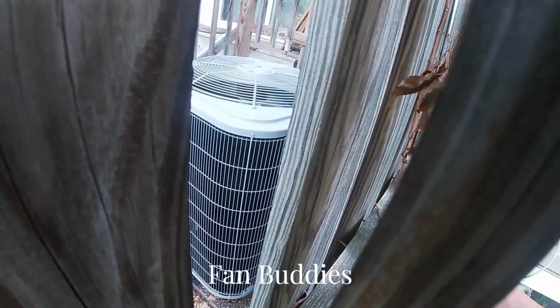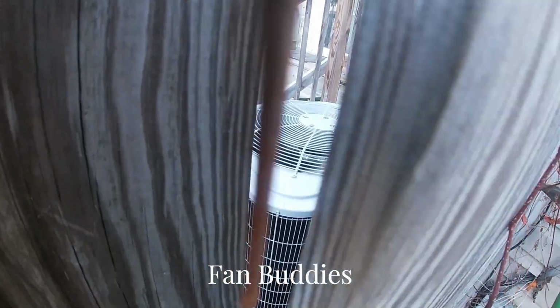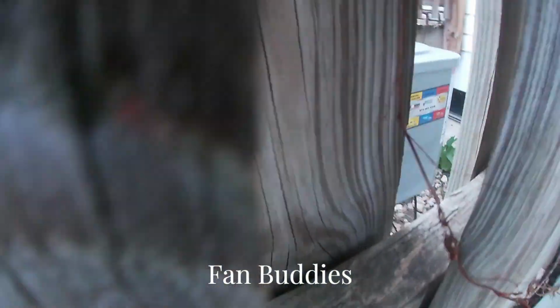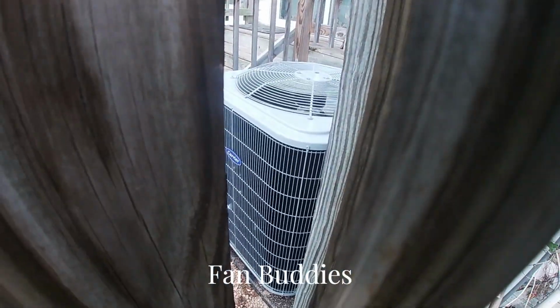It's a brand new Carrier Comfort Series air conditioner. I'm pretty sure that's a Copeland scroll. And this thing is from, yep, 2024. My first 2024 unit. If I zoom in here, you may not be able to see it that well, but it says 20224, so the 20th week of 2024. It says the exact year on the serial number. It's kind of funny. And this thing is a 3-ton. So it's actually a little bit bigger.